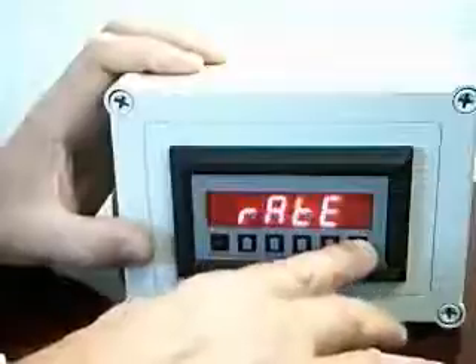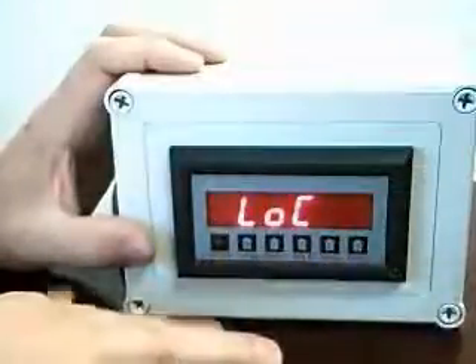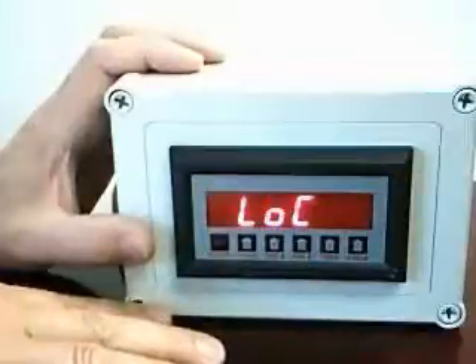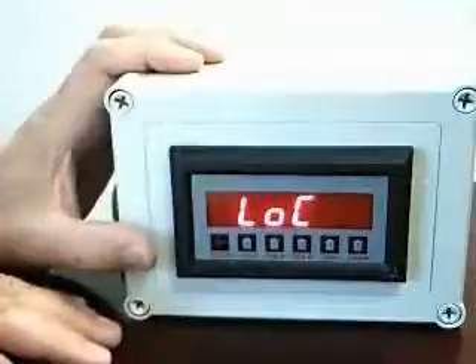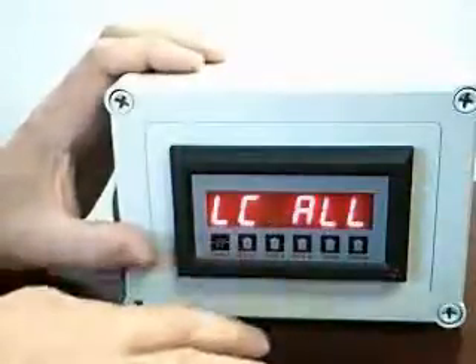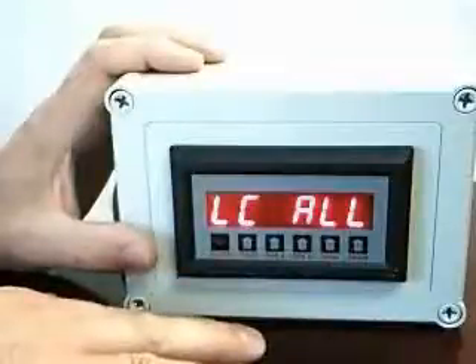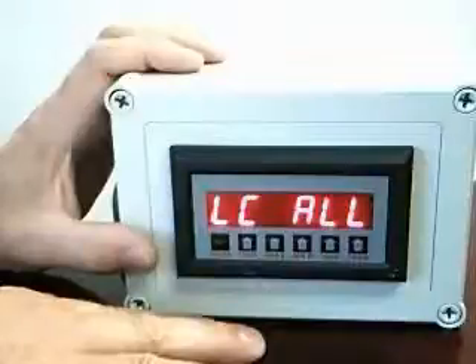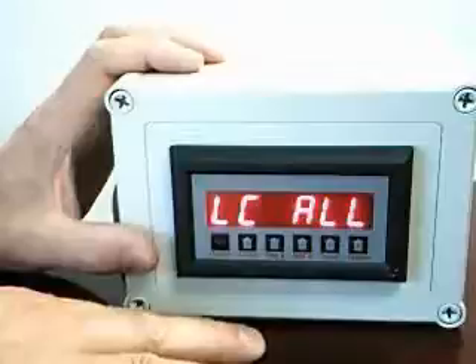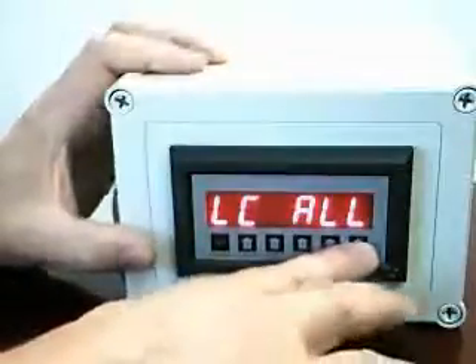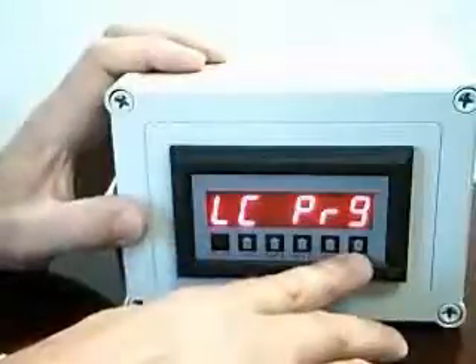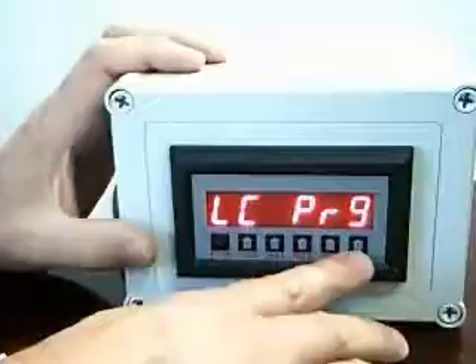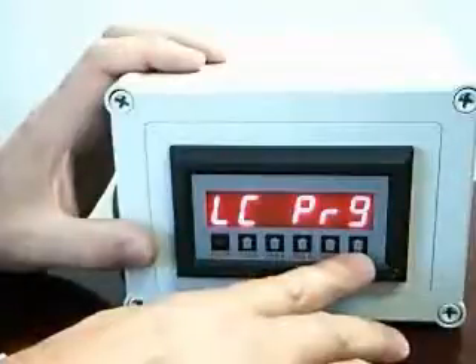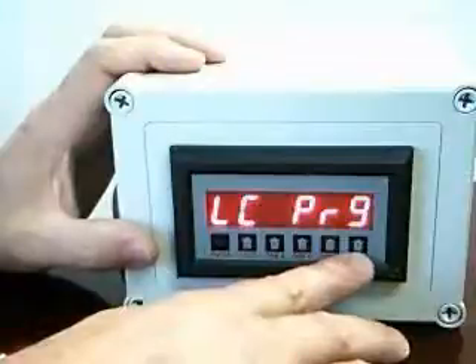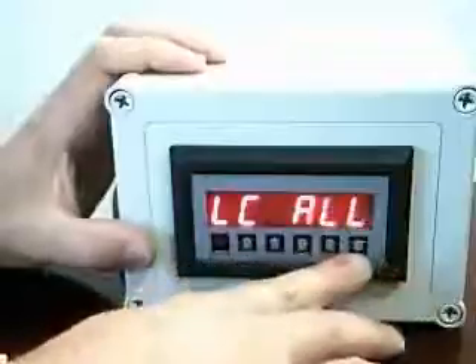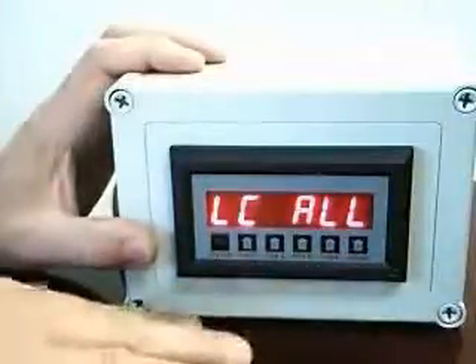Again, pressing the program button until you see lock, which has the parameters associated with the lockout codes. Hitting enter here, you can see that the unit can either permit you to lock out all parameters, and lock all will block access to the set points or to clearing of totals, or the alternate selection is just to lock the program. This would still allow you to block people from accessing the setup mode while allowing them to change either set points or clear totals. We're going to assume lock all, since this is the most common one required in real applications.